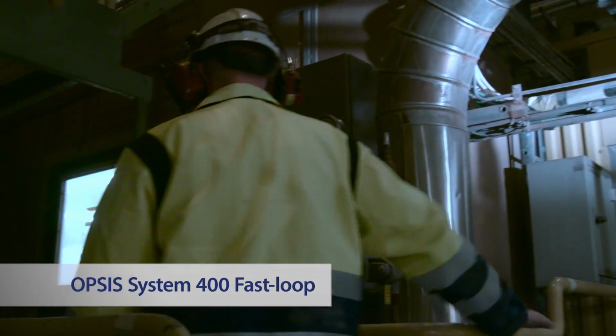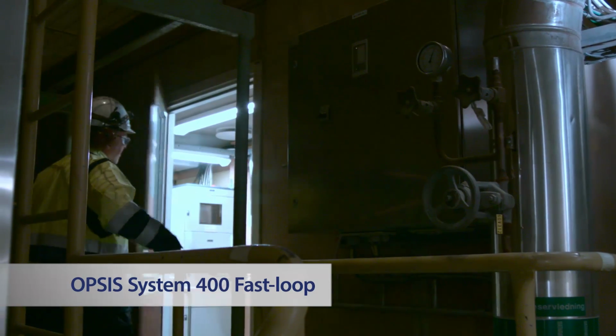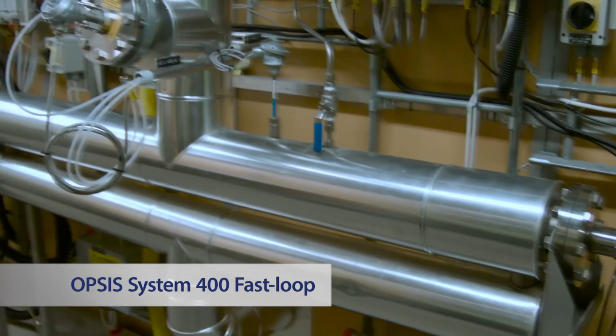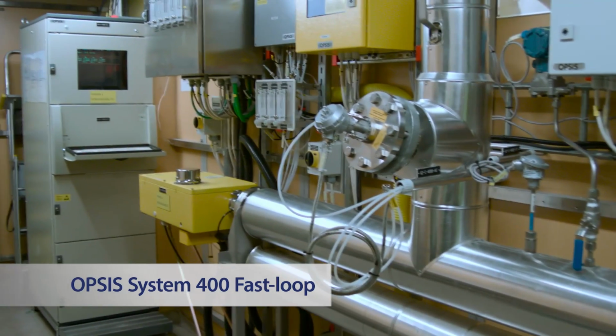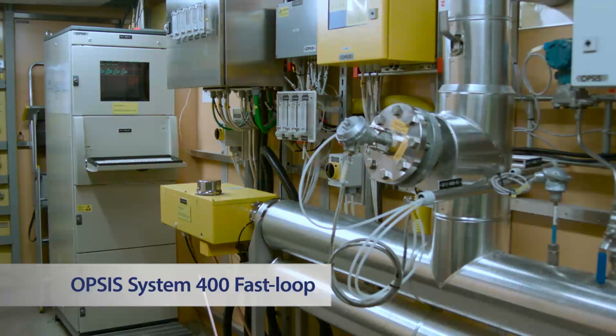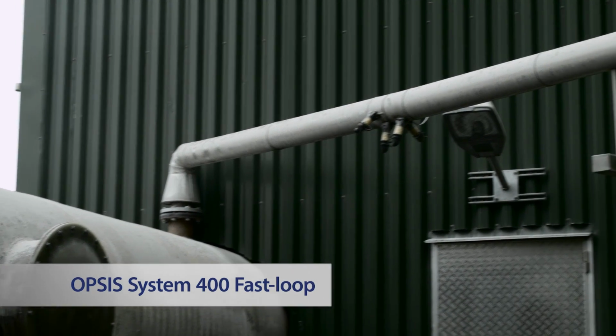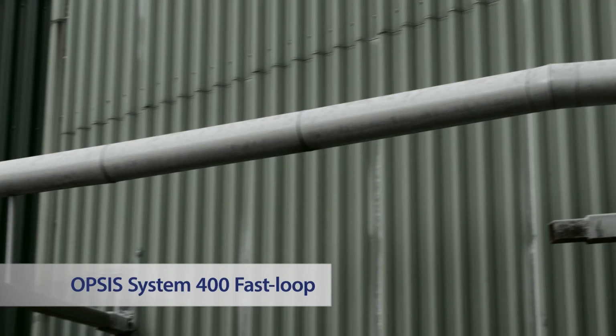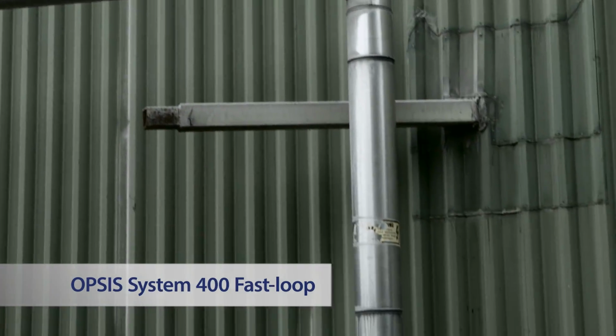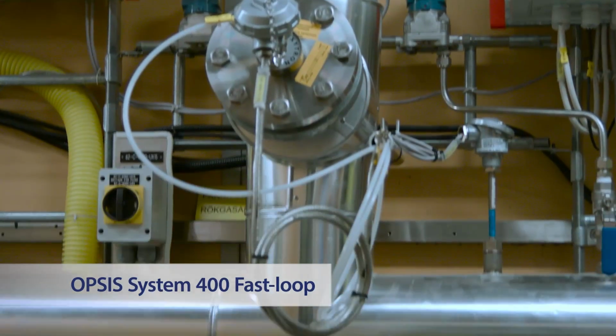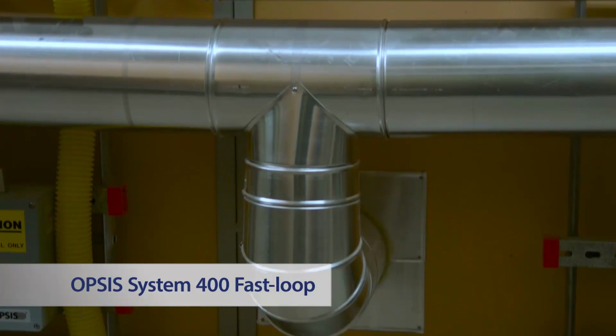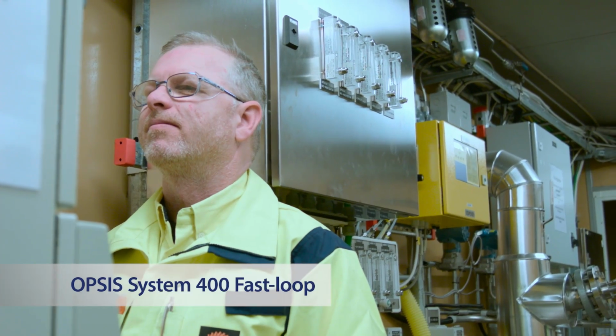This also applies if you want the measurement cell in a separate room with a clean, controlled climate for simpler maintenance. When you install an OPSIS System 400 fast loop in a separate room, you will get a very stable installation. The monitoring equipment is secured on solid ground. The work environment is clean and any maintenance work is more easily carried out. The measurement point can be placed far from the monitoring equipment, and one system can monitor several flue gas stacks simultaneously. Choose OPSIS System 400 Fast Loop if you have a large plant where the measurement points are difficult to access.